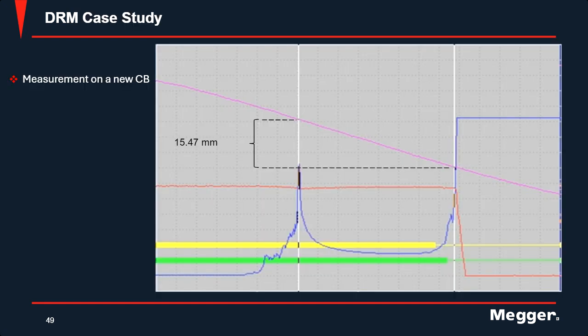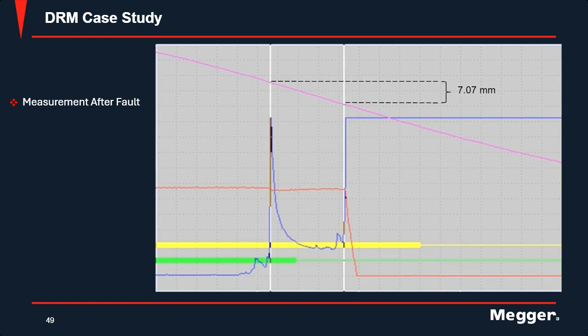So here's an example of a circuit breaker with a new contact. They did the DRM between the 2 points. They can calculate that the arcing contact is 15.47 millimeters. They had a short circuit fault inside the breaker, and when they went back to retest it, they figured out that they only have 7 millimeters left of the arcing contact. So they had to end up actually changing out that arcing contact for a new one, and then we ran the test.